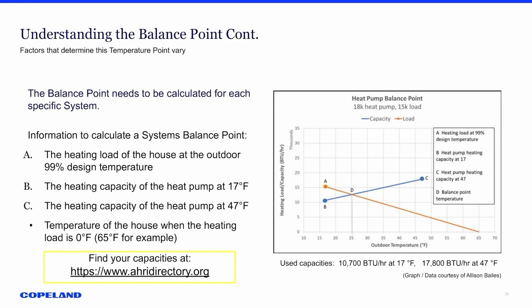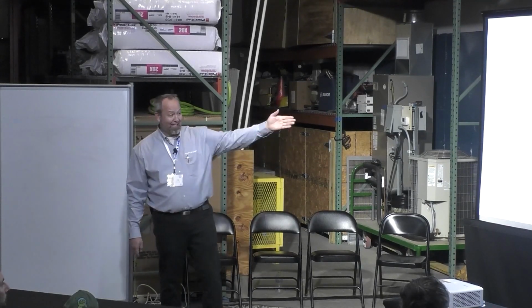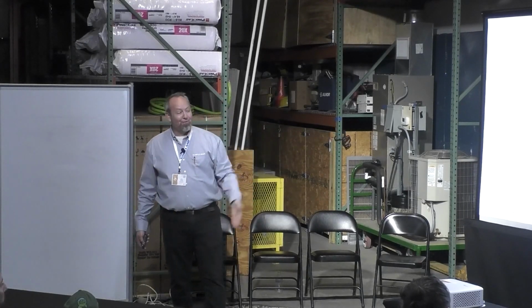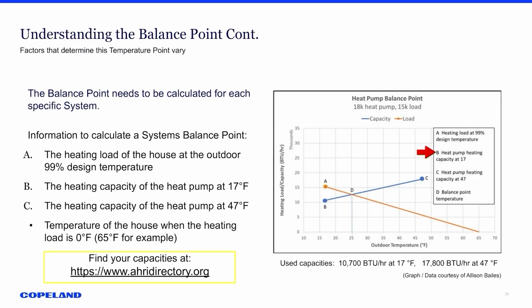And so when you size that, you look at, and actually there's four things that you need to know for the capacity side of things. One is, what's the heating load of the house? The 99% of the design temperature. And that on this, we're going to call A. That's the design temperature of the capacity that we need. And B and C are two numbers, heating capacity of heat pump at 17 and 47. Where do you get those numbers? Those are coming from ahridirectory.org. You can go in there, find your match system. It's the other benefit of having a match system. You actually get numbers that you can find for a balance point. If you're mixing things together, you have no idea what these numbers are. And B is at 17 degrees, what your capacity is. C is at 47 degrees.